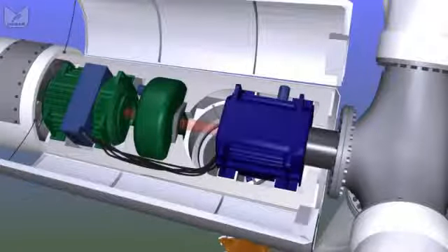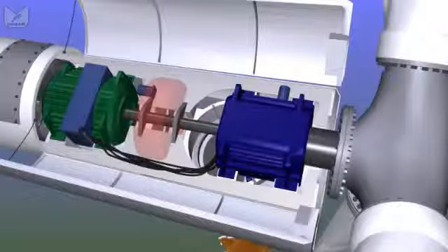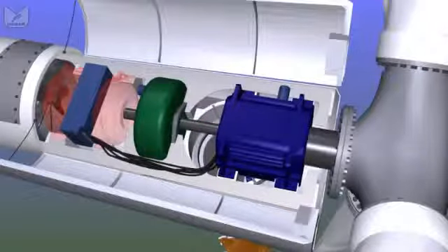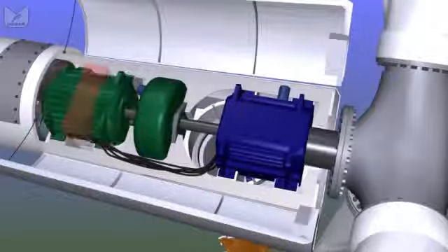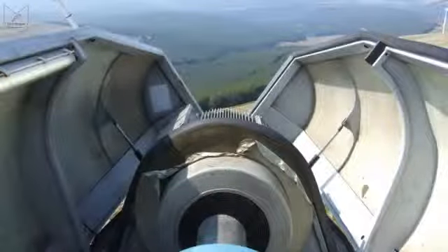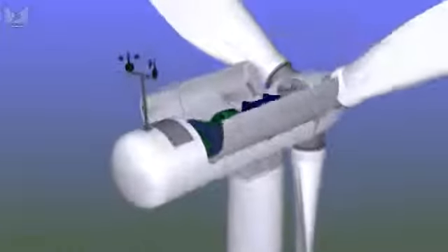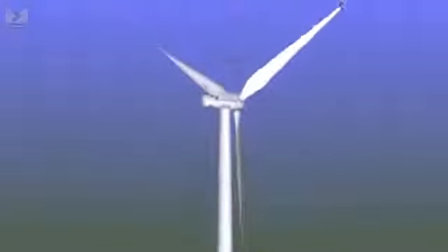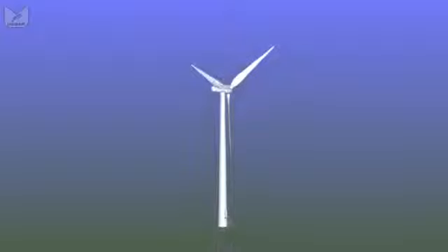then a high-speed shaft through a brake into a generator, and that generator then supplies the electrical power, as I say, at about 690 volts all the way back down the tower to the base. And right at the back we have a cooling fan, as we're generating 500,000 watts of energy inside the nacelle. Some of that is wasted as heat, and without an efficient cooling system there is the potential for the turbine to catch fire. Now, the layout of a larger turbine is broadly similar, but some of the components are in different places, so let's start by looking at the tower section of a typical 2 megawatt turbine.